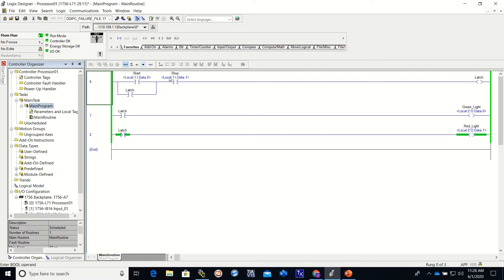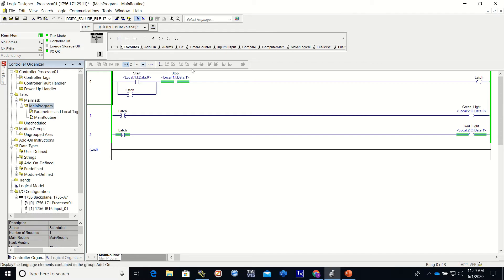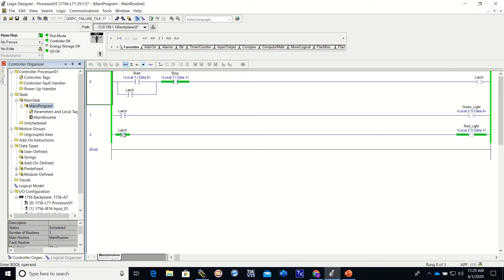It is an examine on, right? So it's examining if it is on, and currently it is on. If I press it, you see it go off. Our start button is an examine on because we want to see when it is pressed. Again, we're going through the normally closed push button of the stop. That's going to hold on this latch. The latch will then go around the start after it's pressed and seal this in.